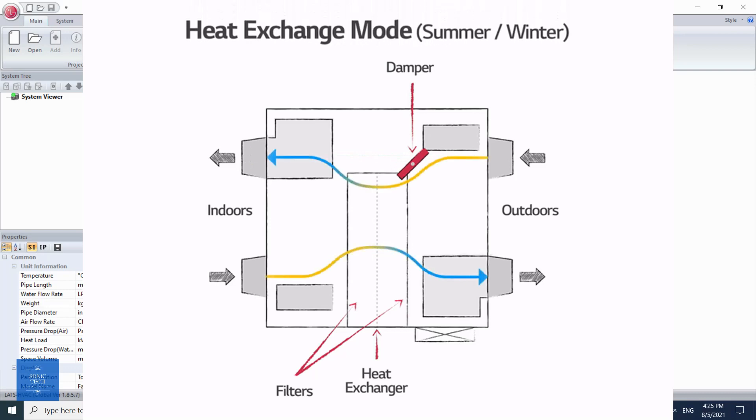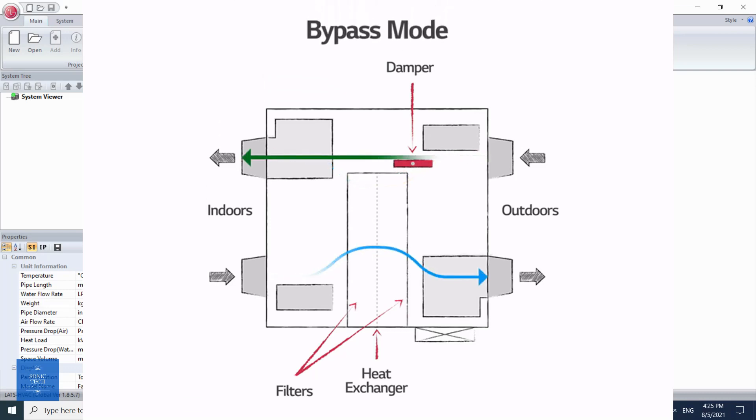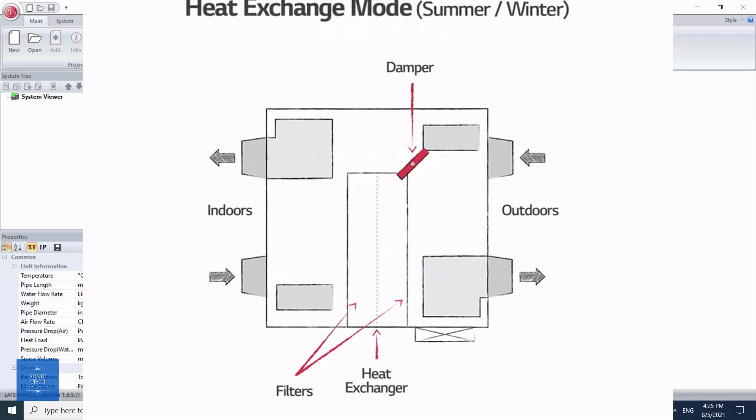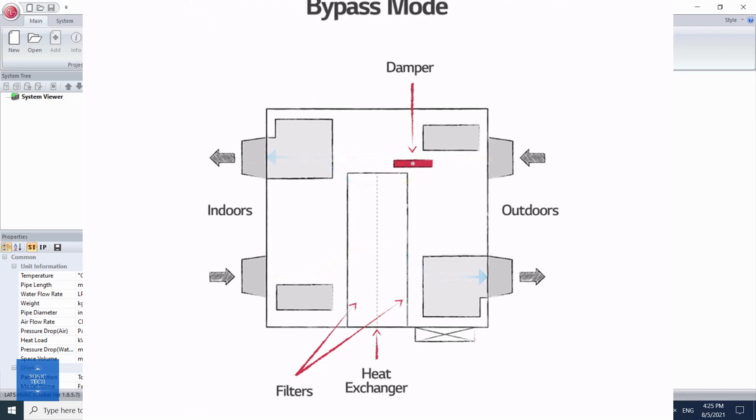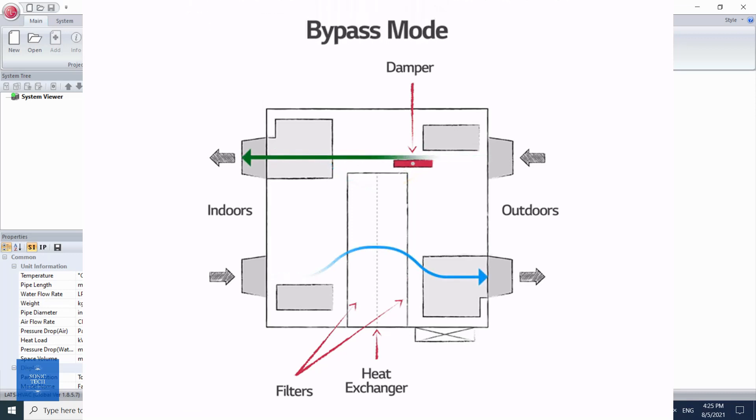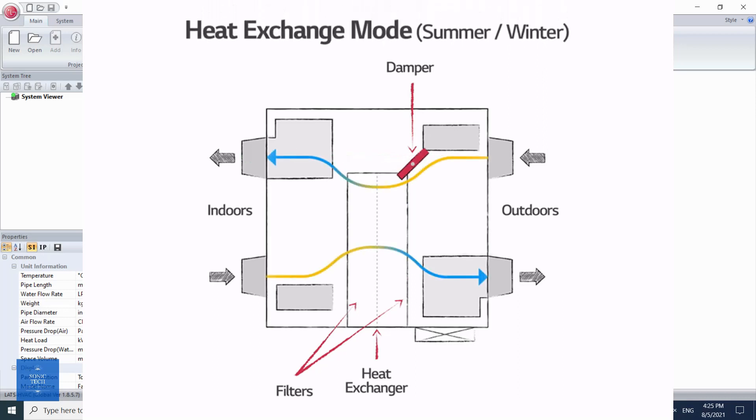How does ERV work? An energy recovery ventilator uses HVAC exhaust air to precondition the supply air, which enters the building at outdoor temperature and humidity. This process recovers some of the heating or cooling output that would otherwise be lost.